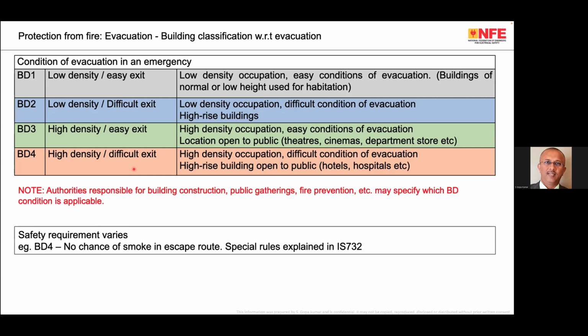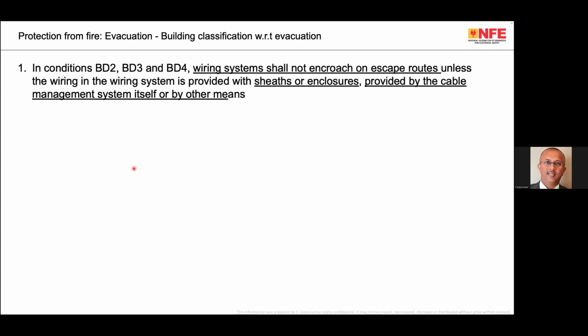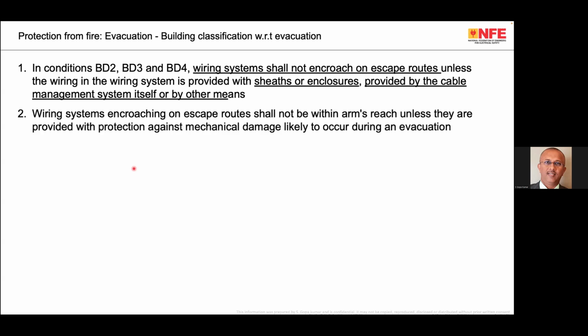Now, the standard tells you the type of additional safety measures required in these locations. Example, in BD2, 3 and 4, wiring system shall not encroach escape route. Several measures are there. I'm only showing you 1 or 2 of the measures. Wiring system shall not encroach on escape routes unless the wiring and the wiring system is provided with sheath or enclosures provided by the cable management system itself or by other means. So open wires are not allowed in the escape route, which is, I would say, very common in a lot of buildings, especially the government buildings in India.